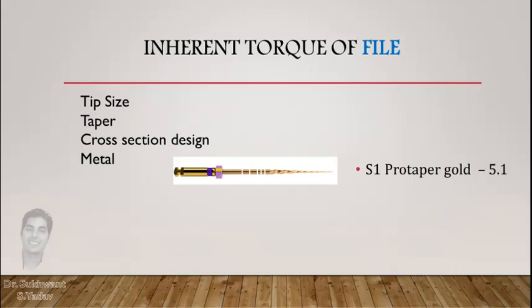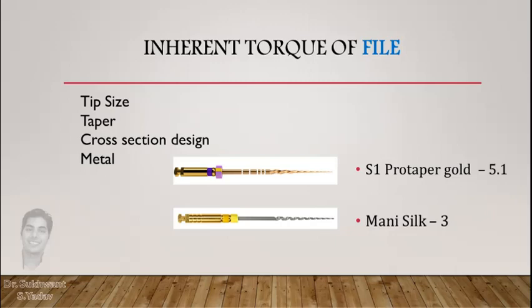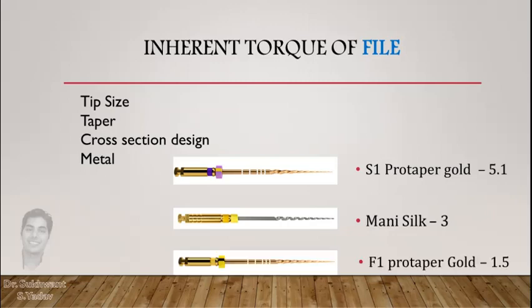This torque limit is not constant — it varies from file to file based on its size, taper, cross-section design, or the metal used for manufacturing. This is called the inherent torque of a file, or the capability of a file to withstand torque without fracture while maintaining its cutting efficiency. For example, it is 5.1 Ncm for S1 ProTaper Gold, 3 Ncm for Mani Silk files, and 1.5 Ncm for the F1 or S2 instrument.